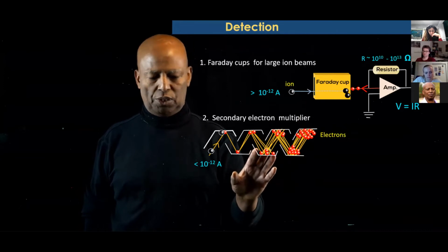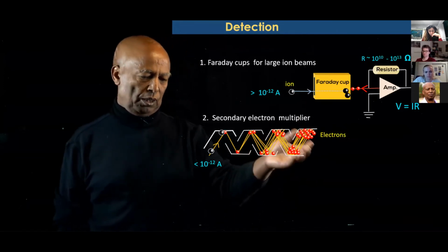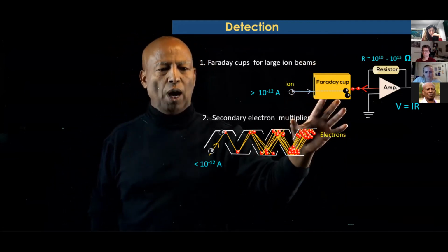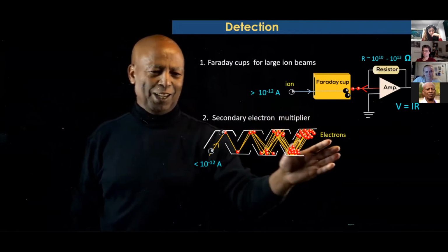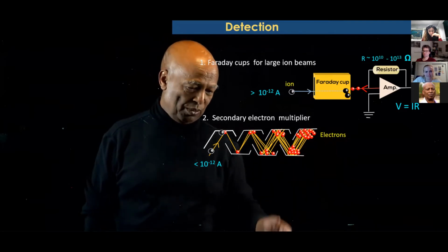Of course, with our secondary electron multiplier, we can do single ion counting. And again, this has been truly amazing. This is the difference between why I had to do 30 milligrams of zircon when I was young, and now we can do 10 milligrams of carbonate with the same system, or less for that matter.